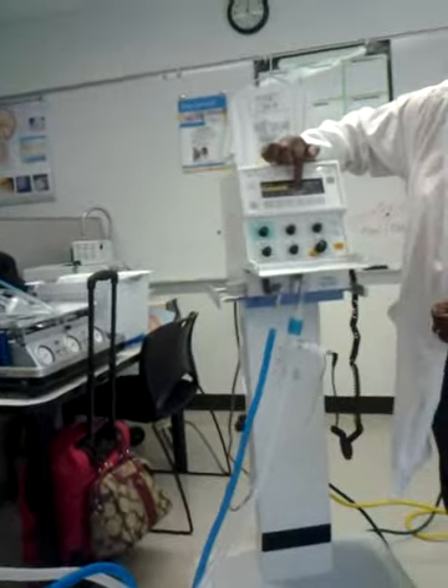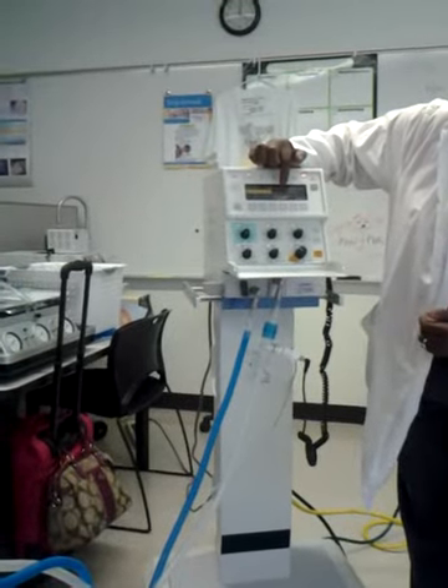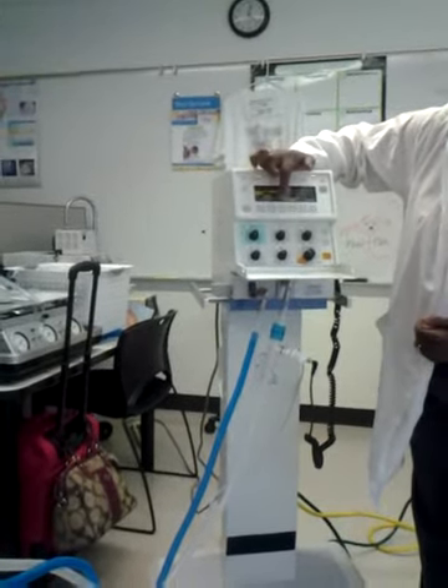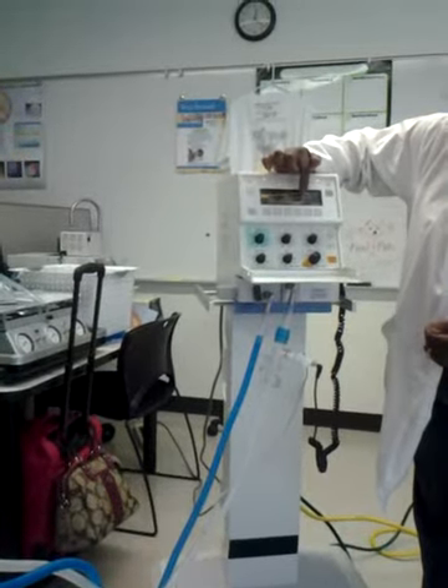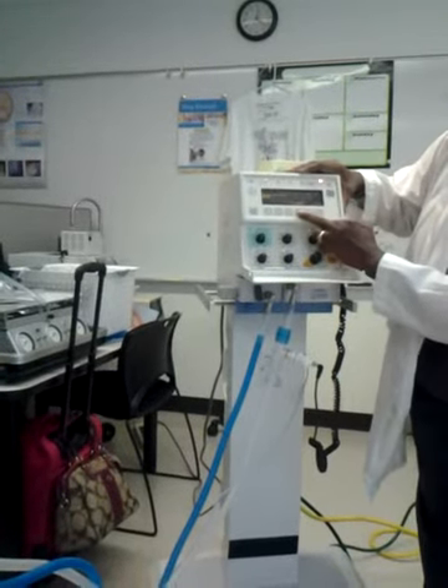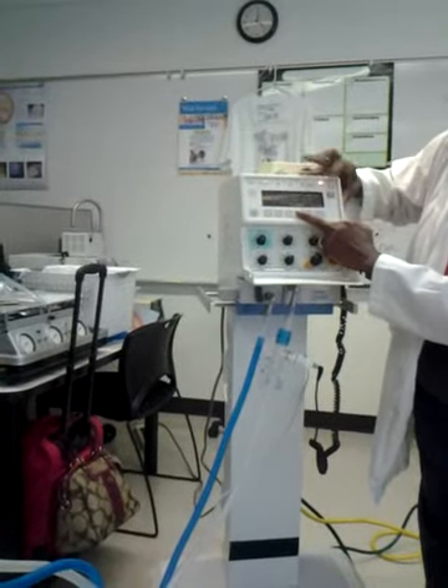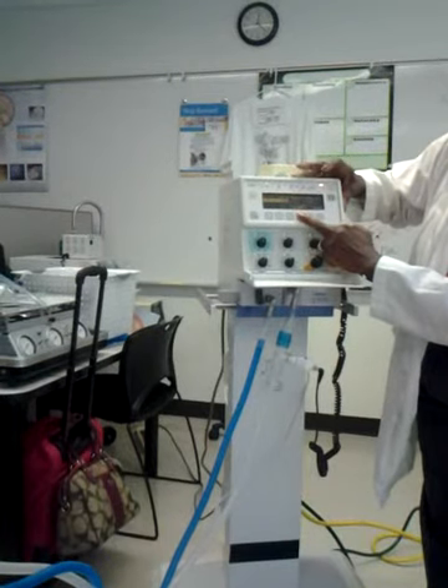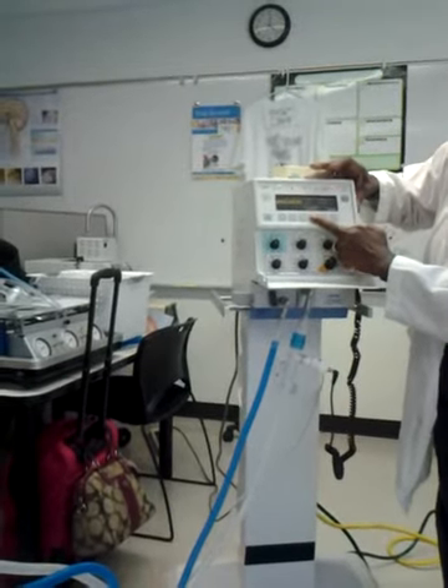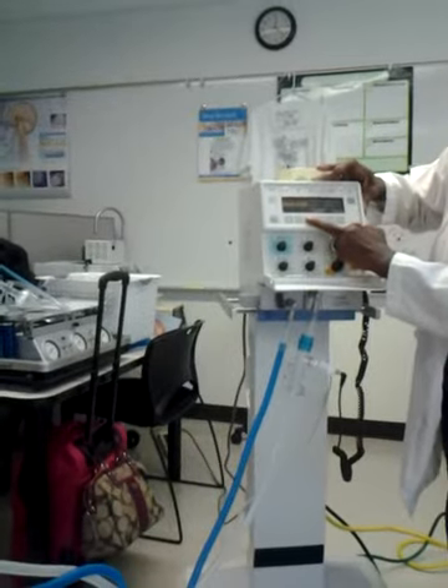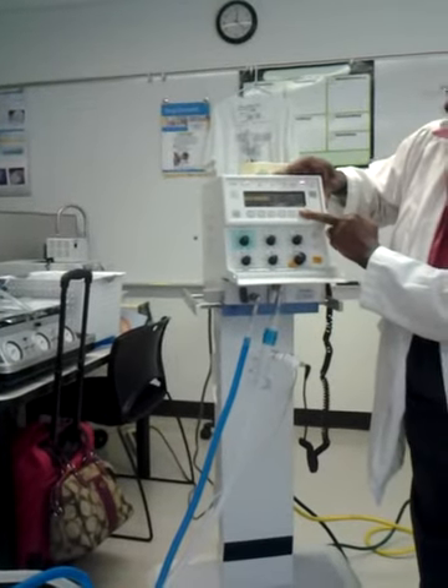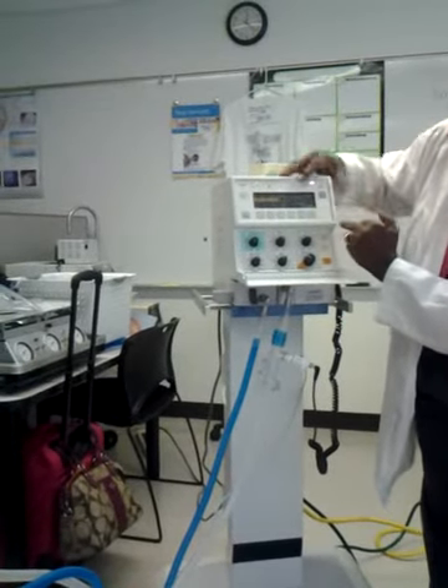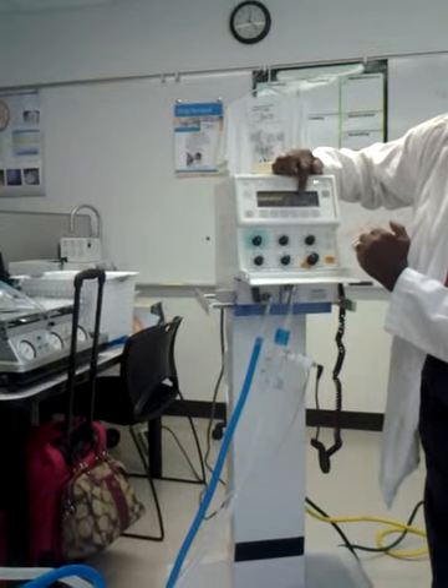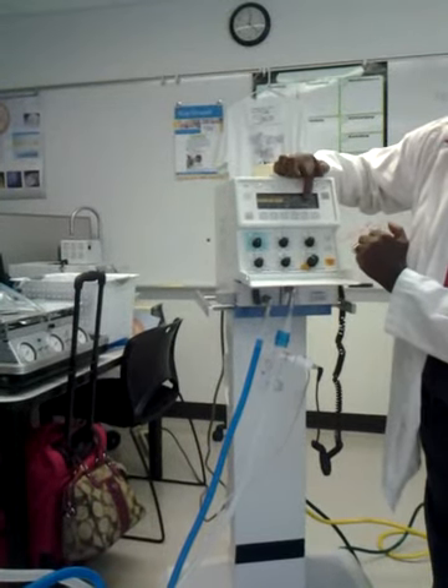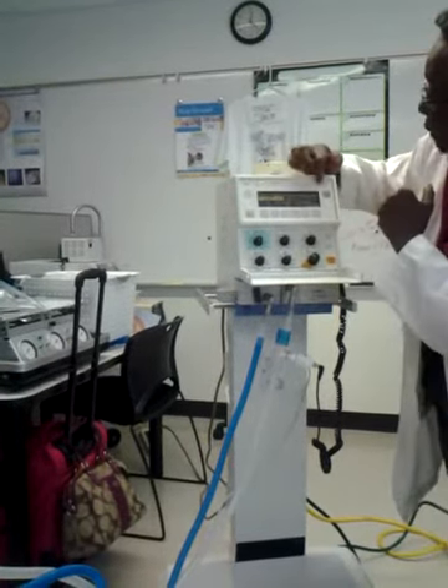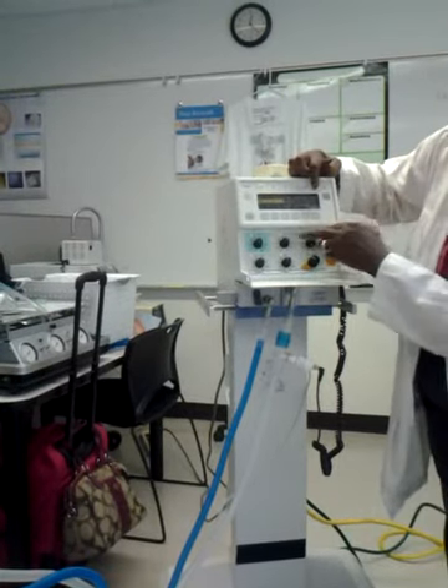You see this little thing right here? It says trigger. This is my sensitivity. You also notice I have a plus and a minus key underneath it. I can make it more sensitive. Okay. See how the bar is going up? Or I can make it less sensitive. If I want to check that, I can. My minute ventilation, my FiO2, and my mean airway pressure are all being displayed here.